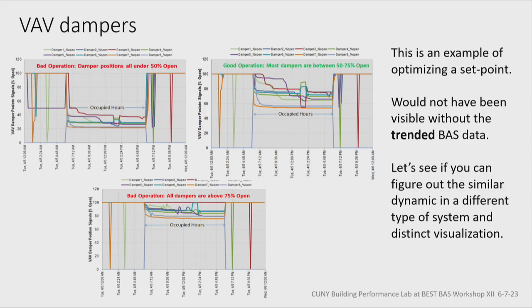I hear you, but I would contend that, whether it's heating or whether it's cooling, the damper positions are showing you the relationship of the amount of air that's getting into the room versus the load. It's not showing the amount of air, it's showing the damper position. Amount of air is CFM.